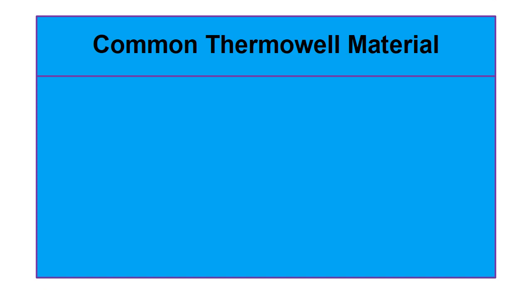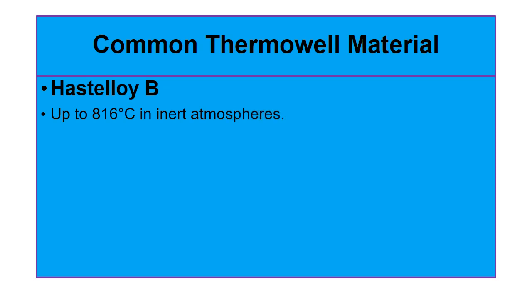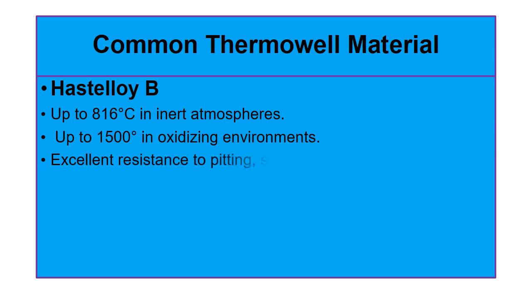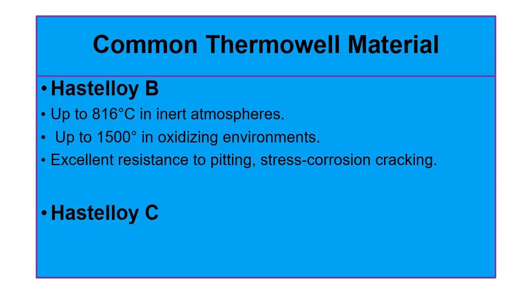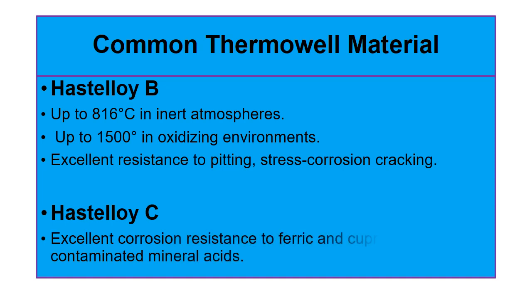The next material we are going to discuss is Hastelloy B. Hastelloy B can be used up to 816 degrees centigrade in an inert atmosphere and 1500 degrees centigrade in an oxidizing environment. It has excellent resistance to stress corrosion cracking, and excellent corrosion resistance to ferric and cupric chlorides, contaminated minerals, acids, and wet chlorine gases.